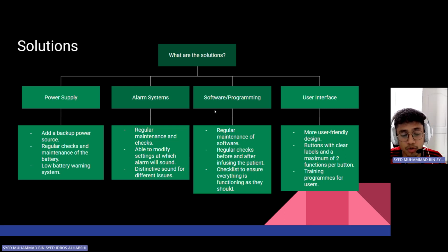Thirdly, for software and programming issues, regular maintenance and checks for the software should be conducted before and after infusing the patient. This is to check that all the buttons are working properly and the liquid can infuse into the patient at the set rate. There should also be a checklist to ensure that everything is functioning as they should. So before infusing the patient with any liquid, they should actually check that all the functions are working before proceeding with the infusion.